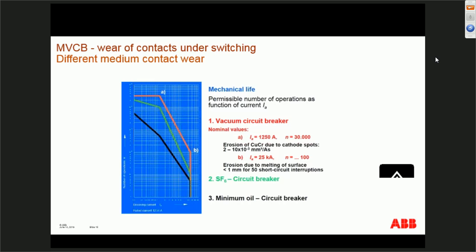Most vacuum interrupters, and people always ask, what is the life of my vacuum interrupter, and how can I project that life during normal operations, say fault breaking or load operations? You can always ask for the VI life damage curve, and this curve can be used to project how many operations you can have at either breaking current or full fault breaking current. You can project that life, whether you see only half of the fault breaking that the breaker is rated for, or say you don't see any faults at all, and then project when you need to perform maintenance on that breaker.